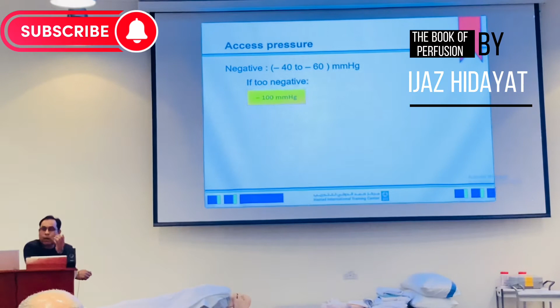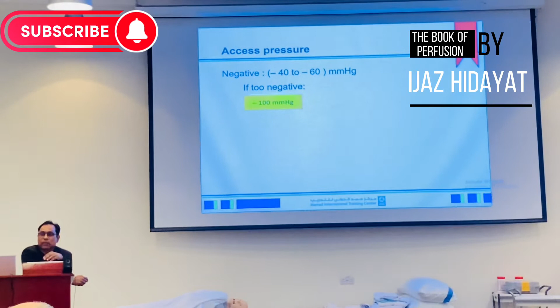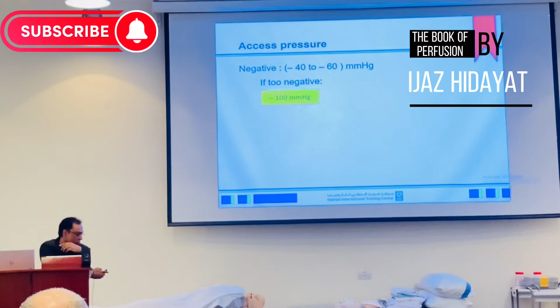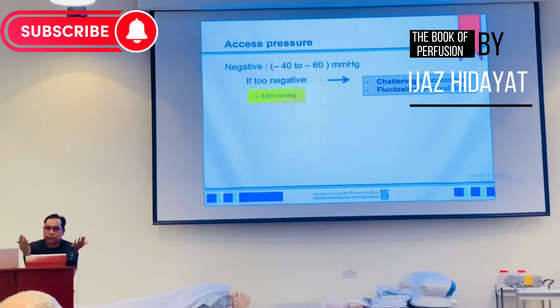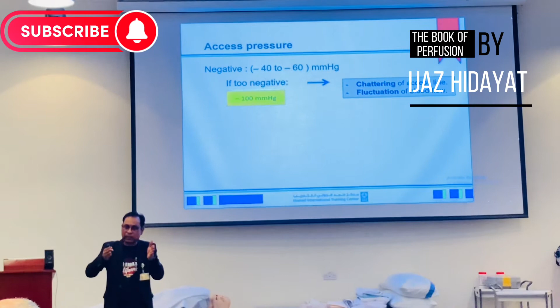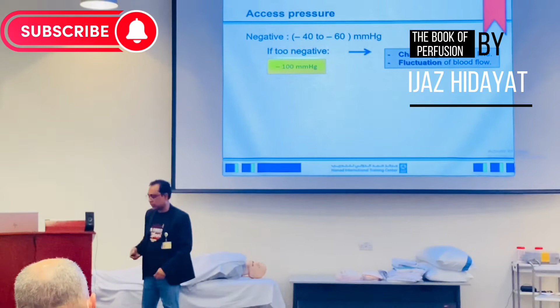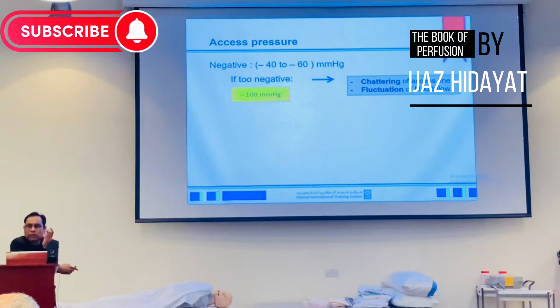If it is more than 100, you have to reduce the RPM, or you have to dilate your patient and increase the volume. It's not bad only to reduce the RPM. Sometimes you need a higher flow. So what you can do, you can go through with your CVP line. If the patient still needs volume, you give some volume and dilate the patient and keep it the same and just decrease your access pressure. See, if the patient has less volume and you are having a higher RPM, there is a chance of chattering. Chattering means the fluctuating of the access line. It means there is less volume, the space of the tube is bigger. Either you need to decrease the tube size or you have to increase the volume of the patient. So the chattering can lead to cavitation. So what you can do is you have to reduce the RPM.